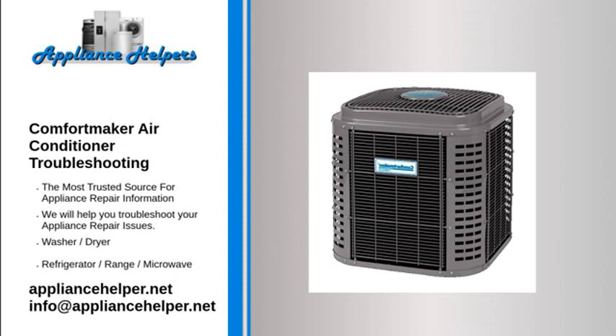Comfortmaker Central Air Conditioner is noisy or loud. The condenser fan motor has bearings that can wear out over time. When the bearings are worn out, they make loud noise. To check the bearings, try rotating the condenser fan motor by hand. If the motor does not turn smoothly, replace it.